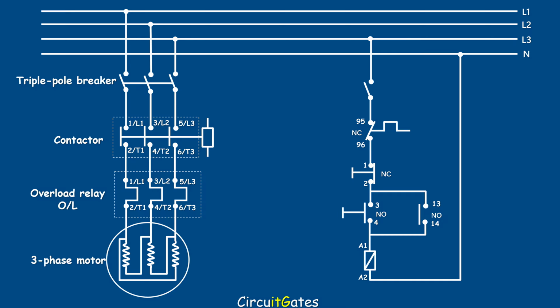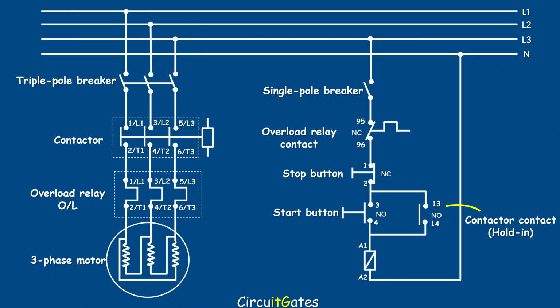next coil. The control circuit consists of a single pole circuit breaker, an overload relay contact, a stop button, a start button wired in parallel with the 13 14 contactor contact, and the contactor coil. To understand how components are connected in series or in parallel, we have a separate video on that. Check out the video link in the description down below.